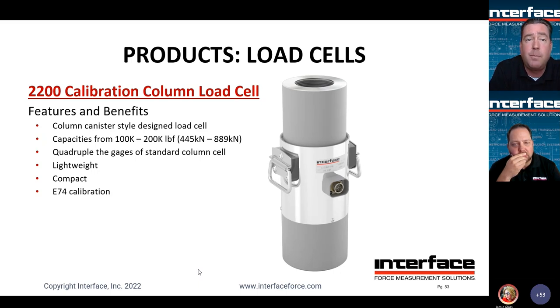For our calibration grade column cells, we do a couple of things different from our standard columns. Much as we did with the 1800 series, we actually quadruple the number of gauges on the load cell, trying to reduce moments and eccentric loading sensitivity to provide better performance and better repeatability. These are much more lightweight than the 1800 and 1600 load cells, a lot more compact, especially radially, and are also included with an ASTM E74 calibration.